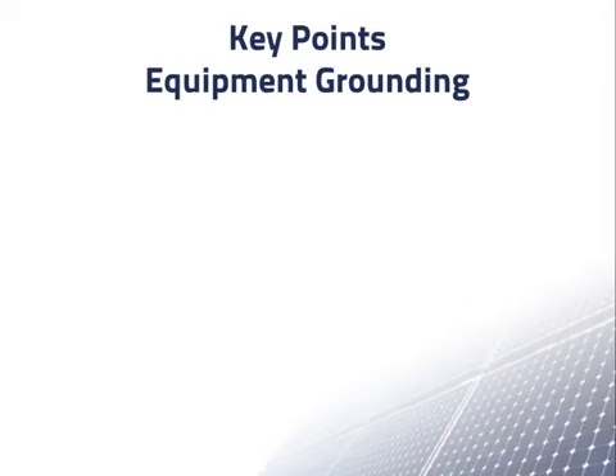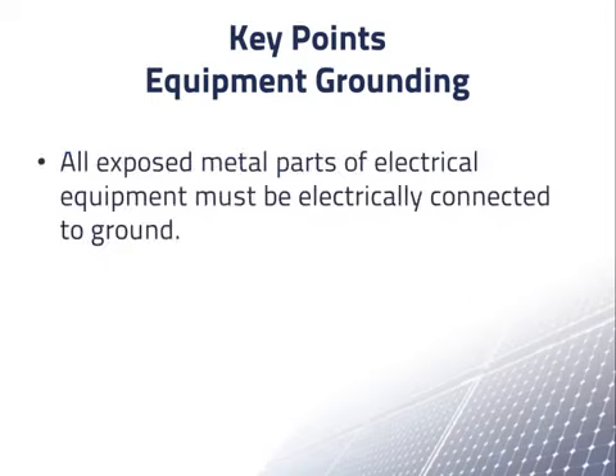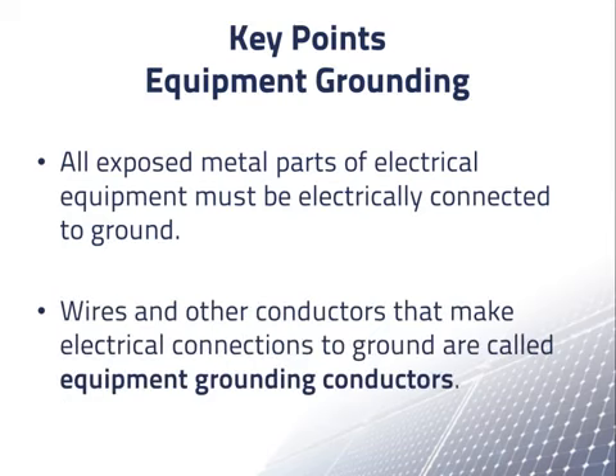In summary, let's go over the key points on equipment grounding. First and foremost, all exposed metal parts of electrical equipment must be electrically connected to ground. This is for the safety of people who might touch the metal. Wires and other conductors that make electrical connections to ground are called equipment grounding conductors. There are many detailed requirements for these conductors and the connectors that make the links to ground. We could only touch briefly on these.